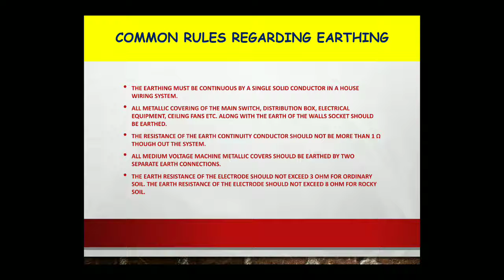Number 4, all medium voltage machines' metallic covers should be earthed by 2 separate earth connections. One is known as the system earthing, another is the equipment earthing. Number 5, the earth resistance of the electrode should not exceed 3 ohm for ordinary soil, and should not exceed 8 ohm for rocky soil. So these are the common rules of earthing.